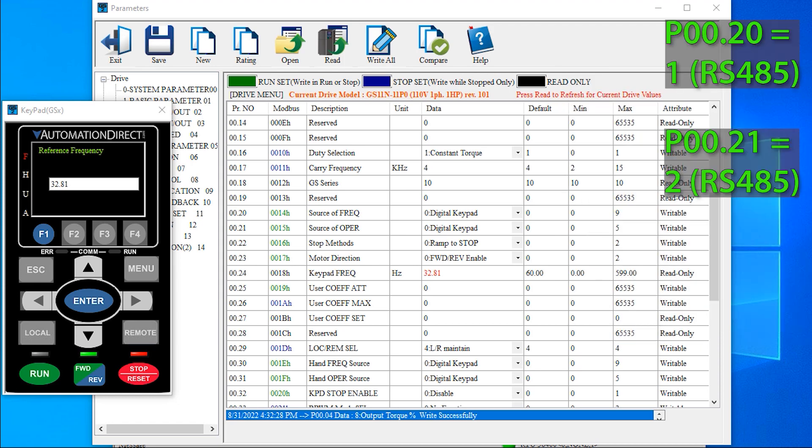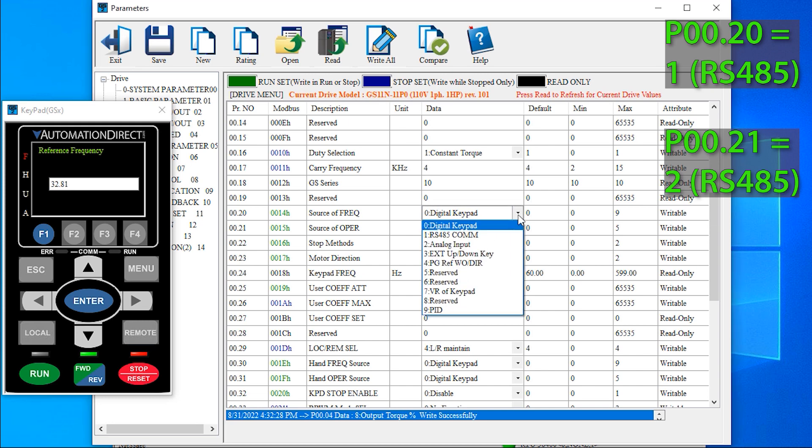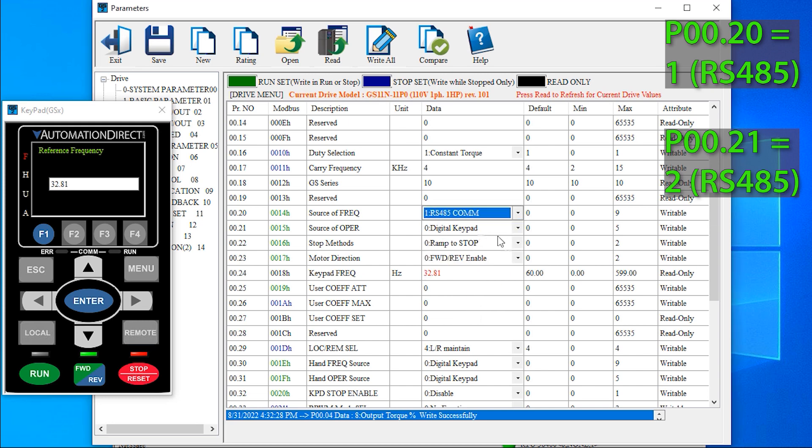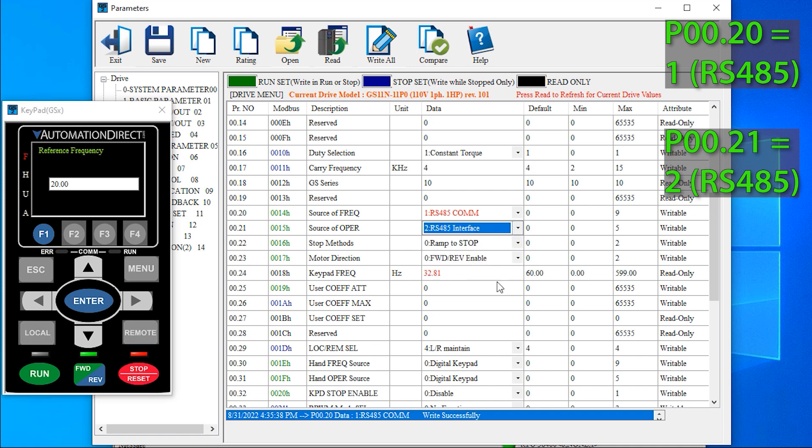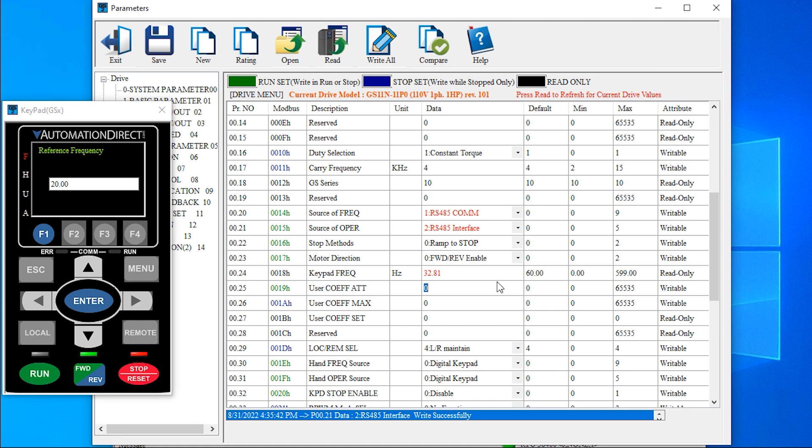We'll set the remote frequency source to RS-485 by setting parameter 0.20 to a 1, and remote command source to RS-485 by setting 0.21 to a 2. It's so much easier to find the parameters by name rather than by number.